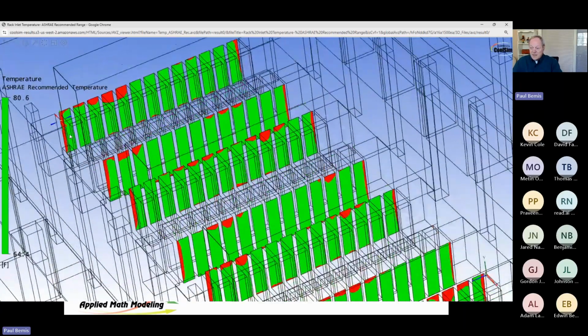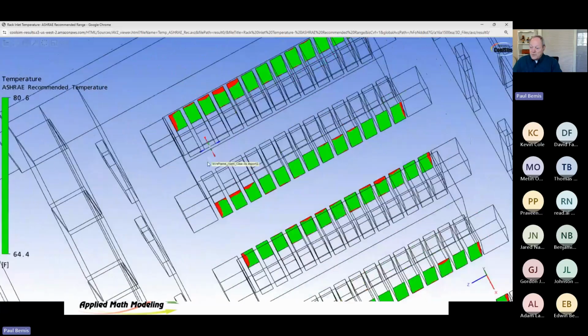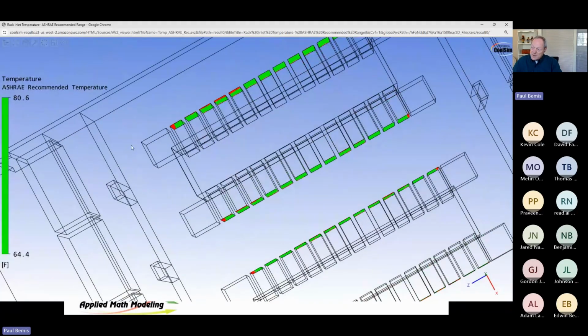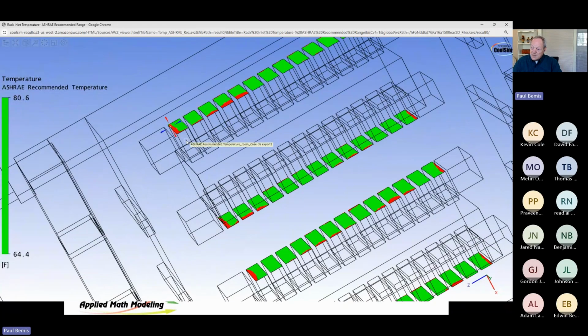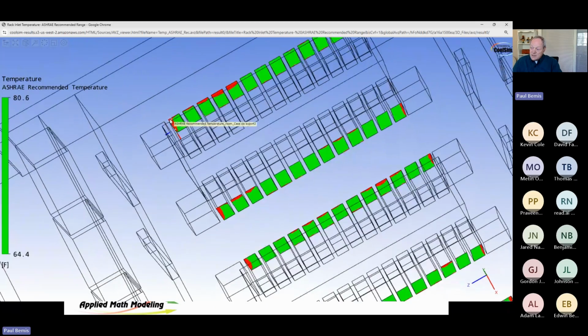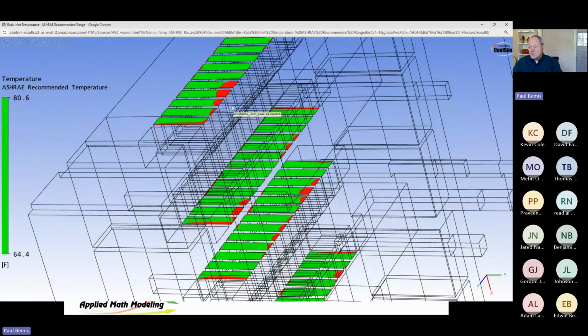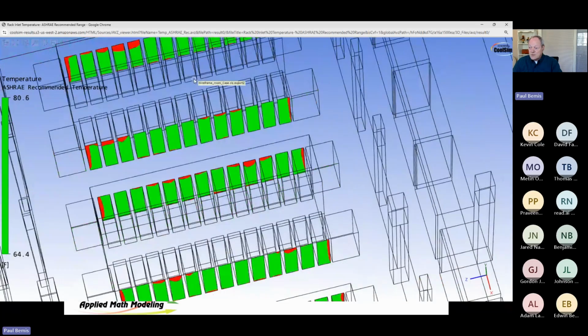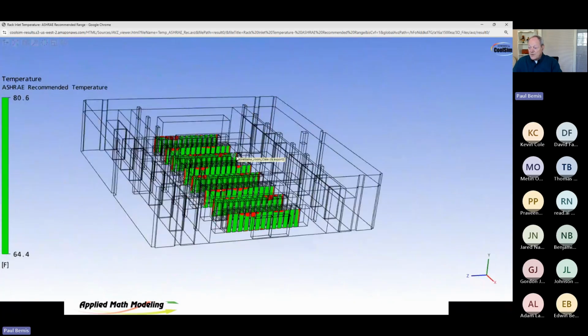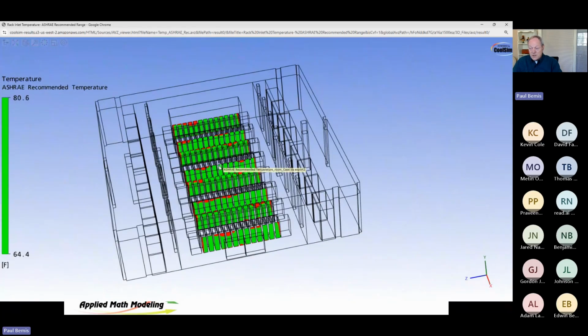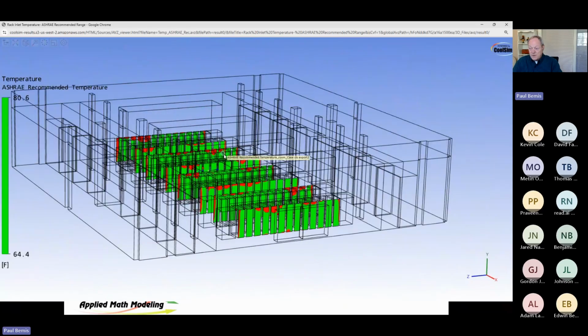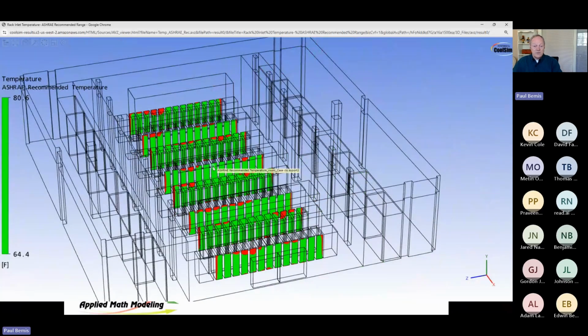Guess why? Velocity's high. So right here, we've got very high velocity air coming from out of this air handler by this rack, and it's causing that rack rail to leak. And I've got some trouble up top here too. That's usually related to pressure variations. So this is not a good situation. My advice here would be, Mr. Customer, you've either got to do one of two things.